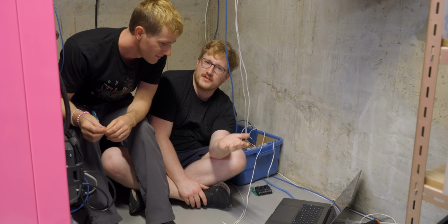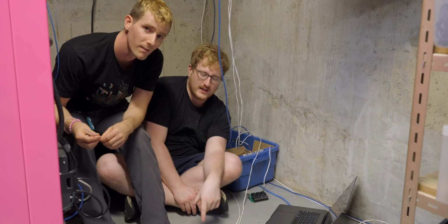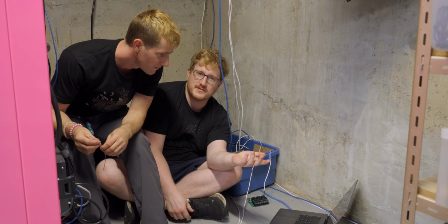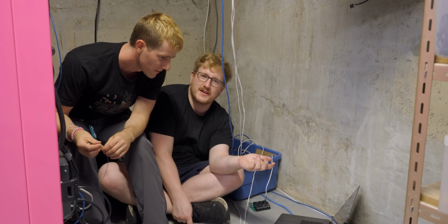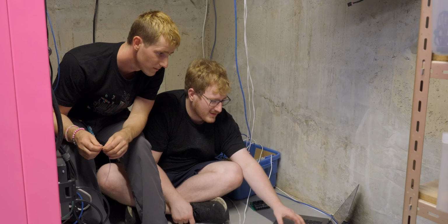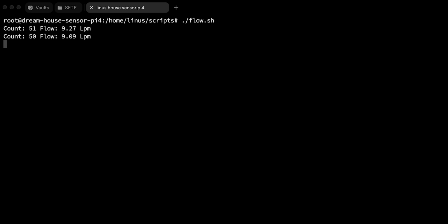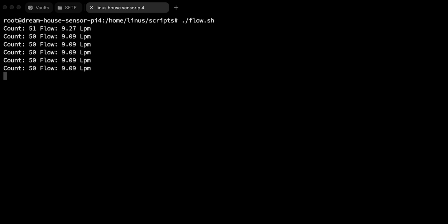We have to interpret the data because all we're getting is pulses. Luckily, they give you a formula: take the pulses per second, or hertz, and divide by 5.5, and that's your liters per minute. So I made a little script to do that. Hey, 9 liters per minute. So we're getting roughly 50 pulses per second, 50 hertz, which is the heartbeat of the whole setup.